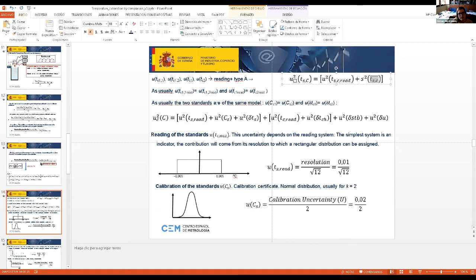we have to consider this, and also that usually we use two standards of the same model, and probably they have the same correction and the same drift. Assuming this, I mean, or maybe the difference of these corrections and the difference of these drifts are very small, so we can assume that they are the same. We have to check this from the calibration certificate and from the history of both standards, okay? So assuming these two assumptions, we can simplify the calculation of the uncertainty of the correction like this.